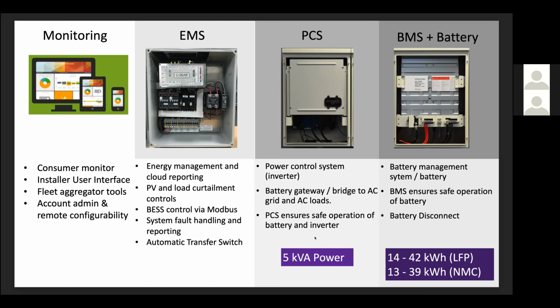It does have quite a bit of surge capability, and that's detailed on the spec sheet that you can see online. It'll go up to 170% of nameplate rating, or 8.5 kVA for up to 5 seconds. It'll do 120% of nameplate rating, or about 6 kVA for up to 30 minutes.